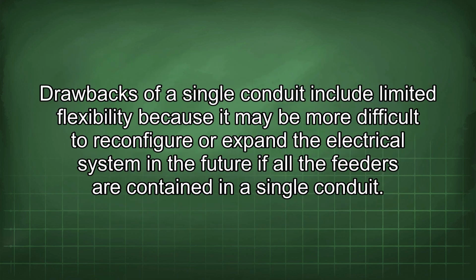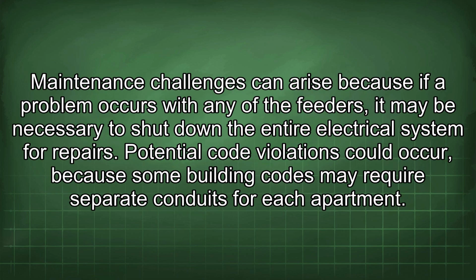Drawbacks of a single conduit include limited flexibility because it may be more difficult to reconfigure or expand the electrical system in the future if all the feeders are contained in a single conduit. Maintenance challenges can arise because if a problem occurs with any of the feeders, it may be necessary to shut down the entire electrical system for repairs. Potential code violations could occur because some building codes may require separate conduits for each apartment.